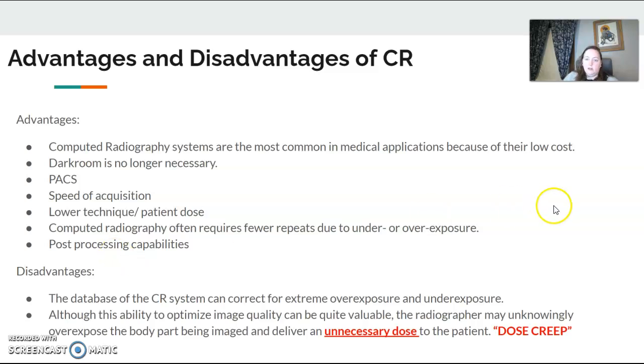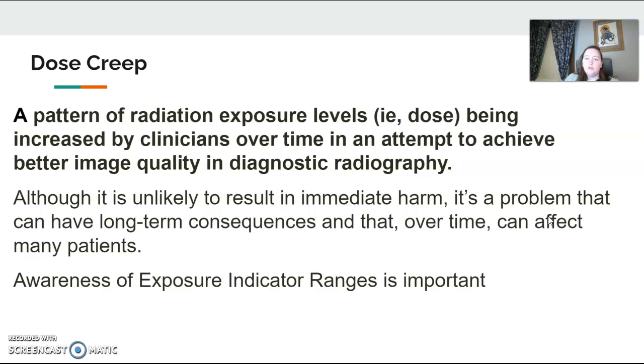One of the disadvantages possibly with digital is something we call dose creep. Dose creep is a pattern of radiation exposures that are being increased by clinicians over time just to make sure they have a quality image. Watching your exposure index numbers and knowing the ranges for your exposure index numbers for each set of equipment is important. Know where your target should be — should I be between 100 and 300? Am I using direct digital? Do I have a grid on? Things like that are really important to be aware of.